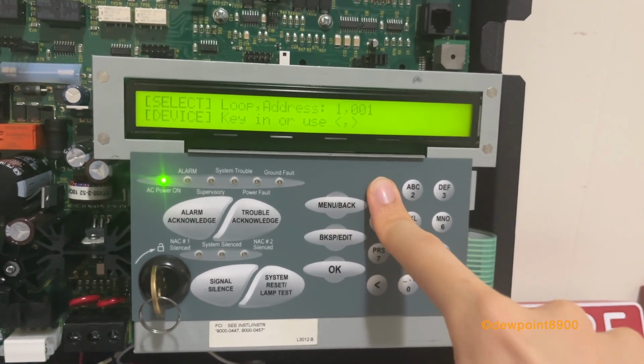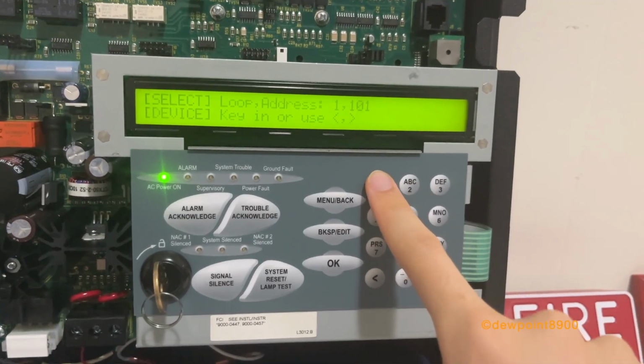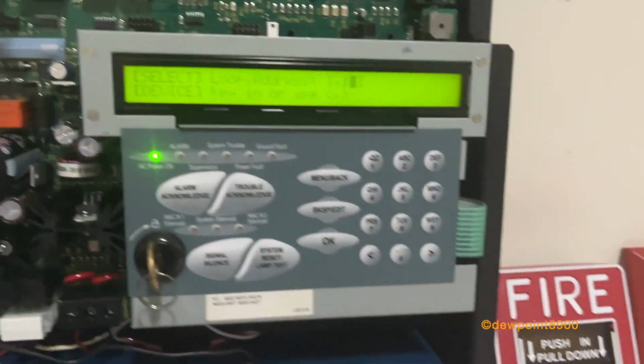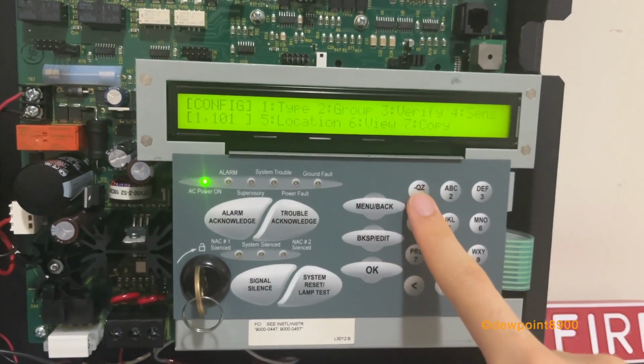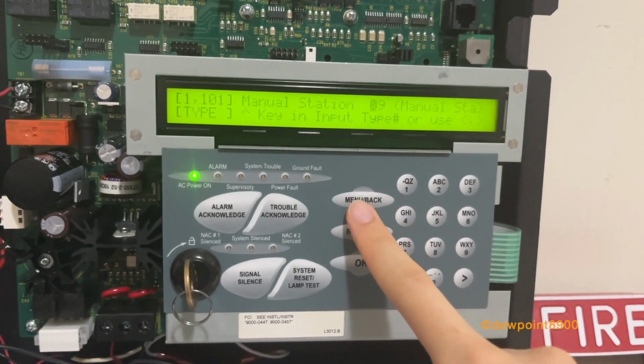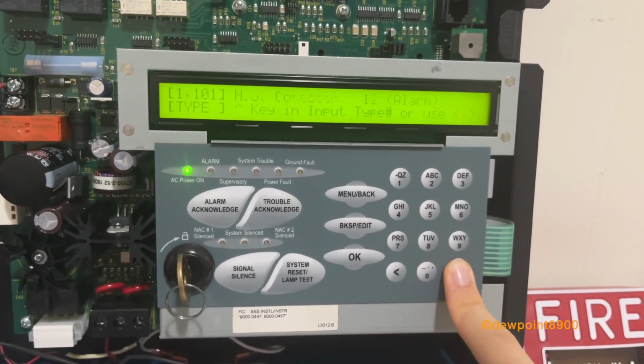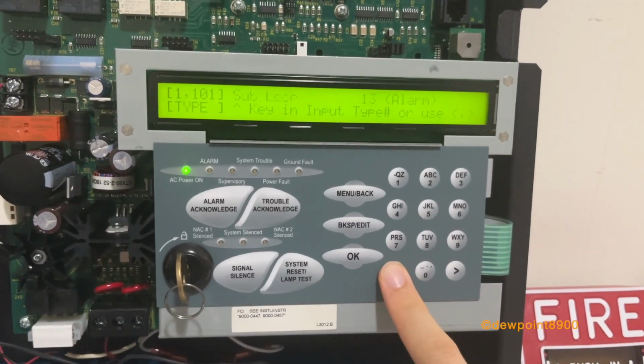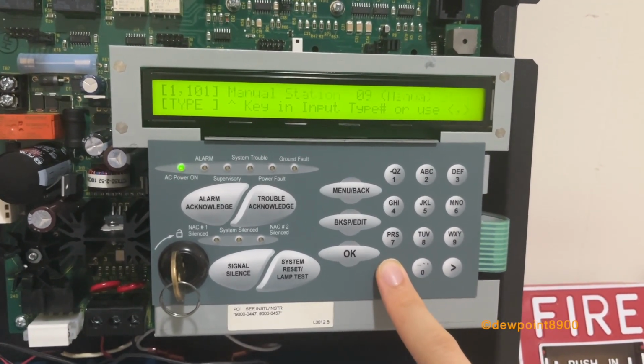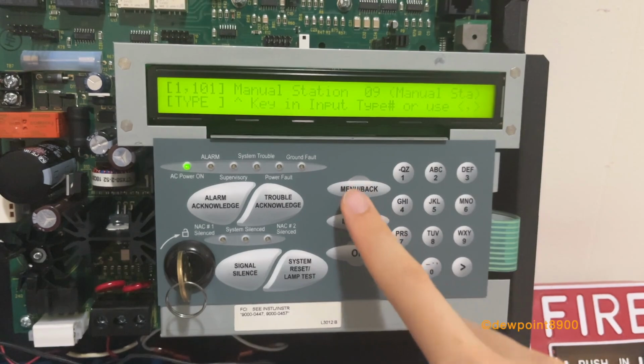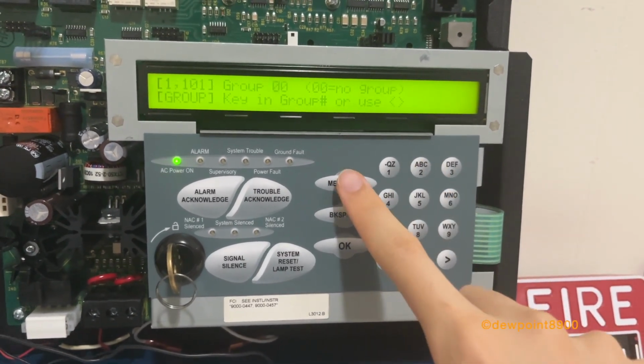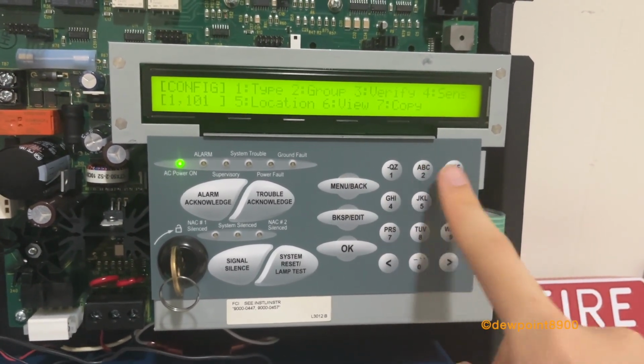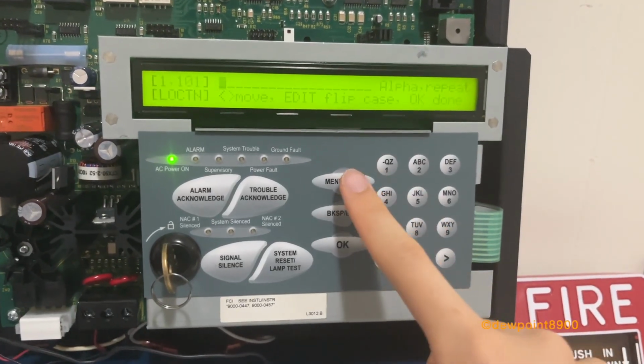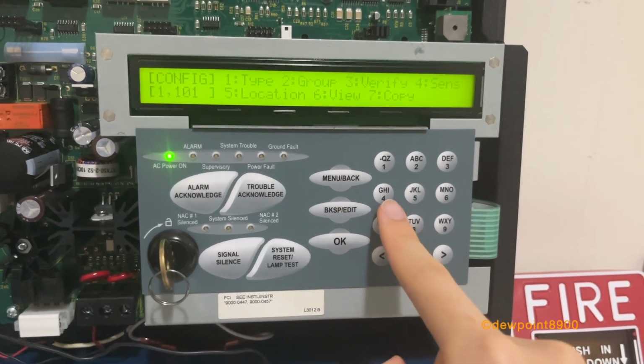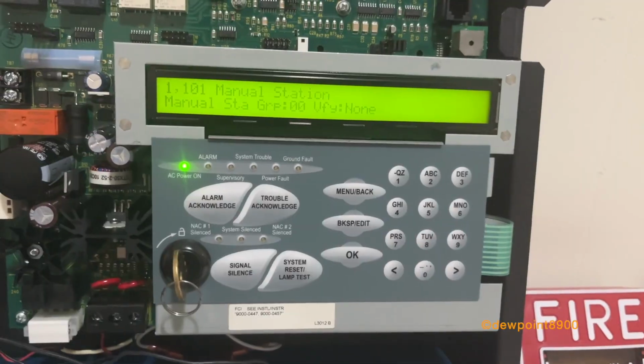Now let's check out a module. Modules start at 100, so 101 is this pull station. You get pretty much the same options. This is a manual station, and there are many different device types that can be configured for this. Save this back as manual station. Group, and then verification and sensitivity don't really matter for a module. Location, and then view. Shows the basic details for this device.